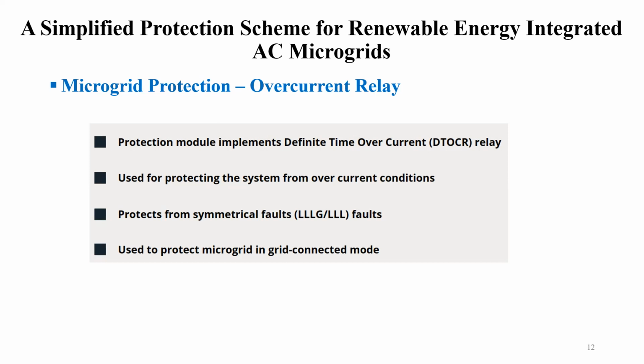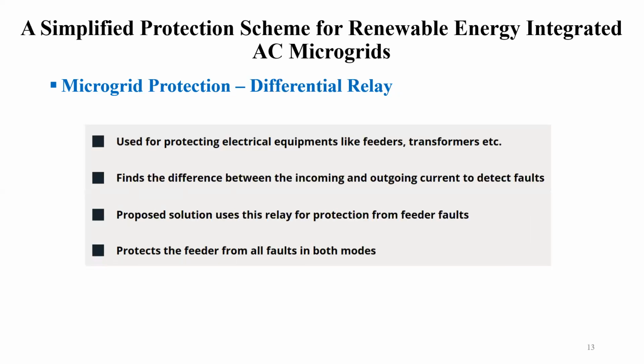So we have simulated it in our simulation. We are using this relay for the analysis. It is used for protecting the system from overcurrent conditions, and the primary purpose is that it protects us from symmetrical faults, that is line to line to line to ground faults, or line to line to line faults. It is used to protect the microgrid in grid connected mode. So remember, this relay will not be used in the islanded mode of operation.